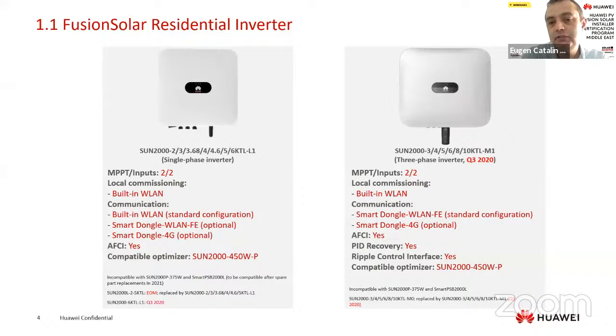This inverter has also the function DC arc fault detecting, compatible with optimizer SUN2000-450W only. It has extra options: PID recovery and ripple controller interface. Possibility to connect a ripple controller. I don't know if in your area it's used, but in some countries in Europe it uses a ripple controller. Will connect in communication port in digital input. This product will replace the old product SUN2000-10KTL-M0.